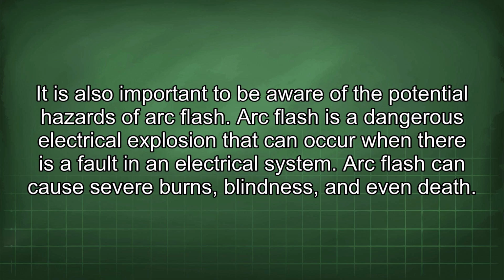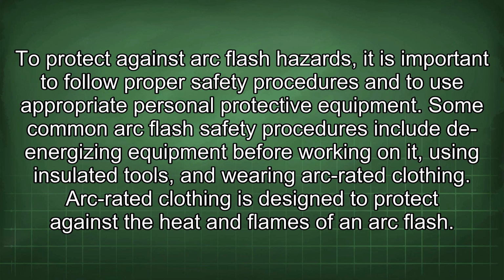Arc flash is a dangerous electrical explosion that can occur when there is a fault in an electrical system. Arc flash can cause severe burns, blindness, and even death. To protect against arc flash hazards, it is important to follow proper safety procedures and to use appropriate personal protective equipment. Some common arc flash safety procedures include de-energizing equipment before working on it, using insulated tools, and wearing arc-rated clothing.